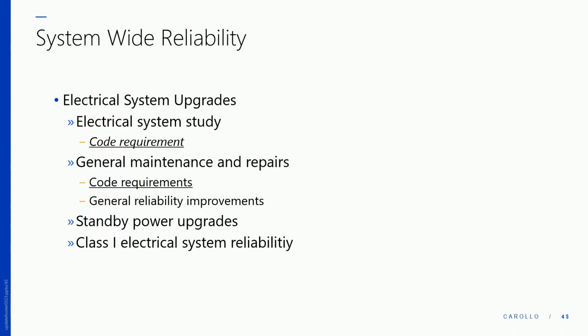and we're going into the Class 1 electrical system reliability, which is a standard that is published by EPA. We're recommending to provide some redundancies to the utility lines, having a standby utility line, so 2 utility lines with redundant transformers throughout. And then that redundancy follows through to your electrical equipment inside the facility. So in other words, we're creating 2 trains of electrical systems. So if one train were to be down for a fault, you have half of the loads, or half of the plant, also with power, so you can continue operations. Okay, so that's part of the breakdown in the study as well.